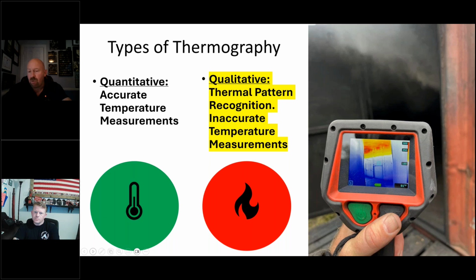In this picture, looking into a container, we have a spot temperature measurement of 91 degrees Fahrenheit, where if we read the actual relative heat indicator on the side, we're reading between 150 to 300 degrees apparent temperatures. Apparent temperatures are a gigantic estimate based on those pre-programmed variables that we can't control.